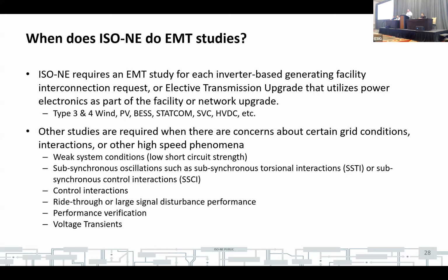ISO New England started doing EMT studies probably about 11 or 12 years ago. There was an SVC going up in the northern part of Maine, which was causing some instantaneous overvoltage issues on some of the wind farms up there. In northern Maine there's a lot of different wind farms, and as part of integrating that SVC, they started looking at the transients and found they needed to parameterize the controls specifically for that SVC for those wind farms.